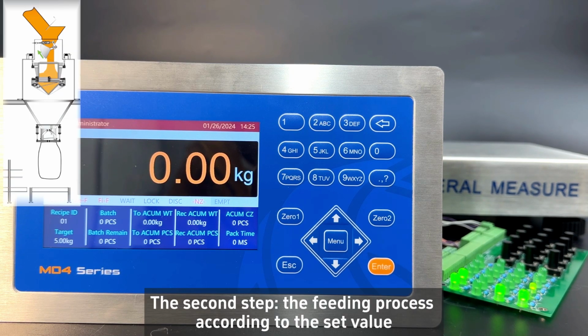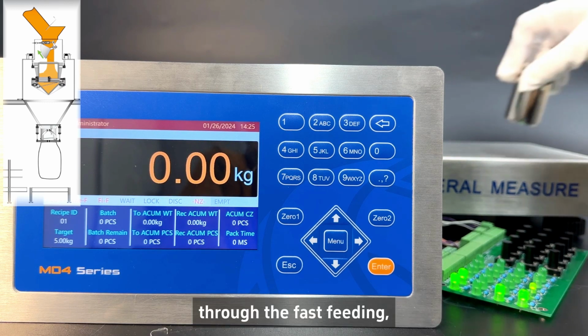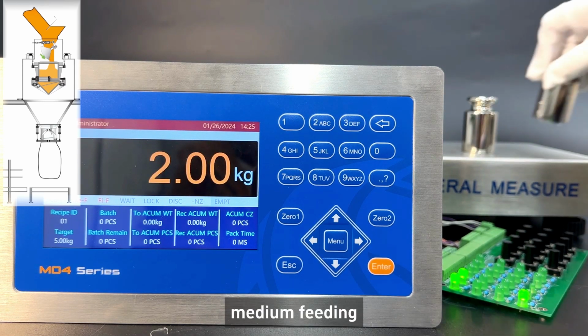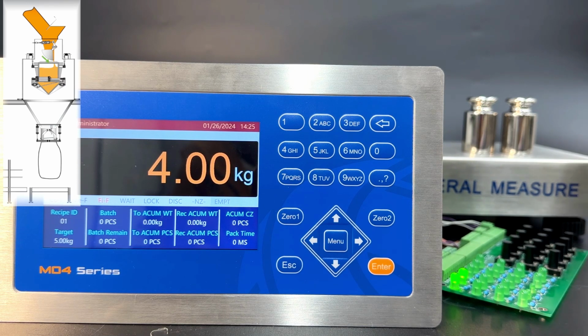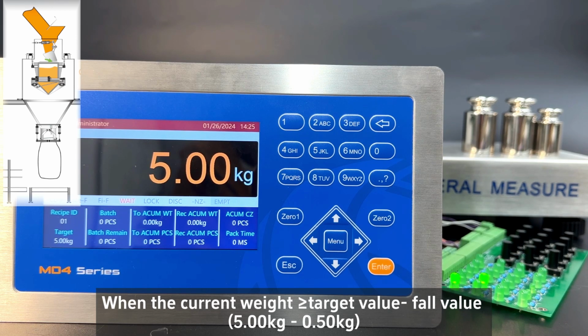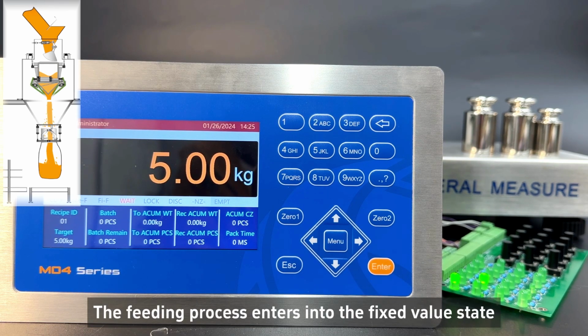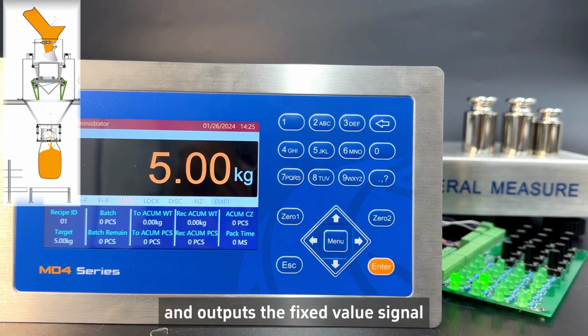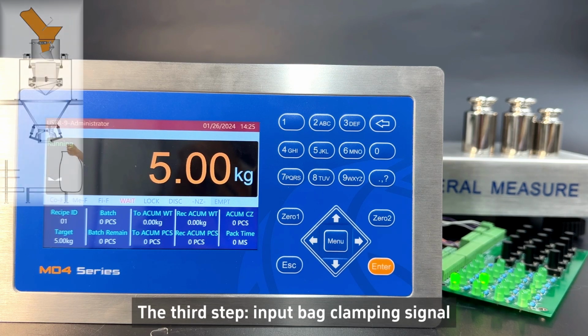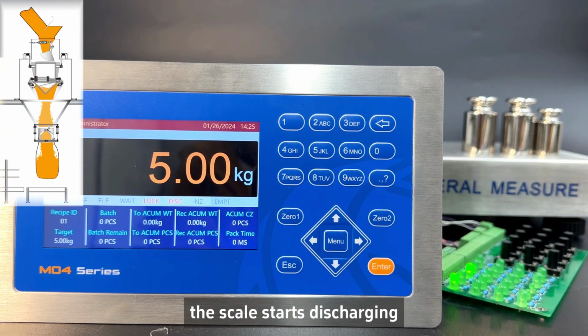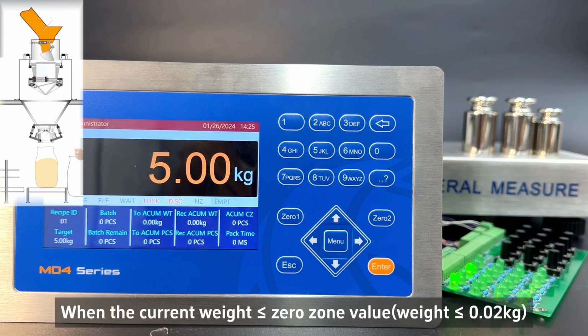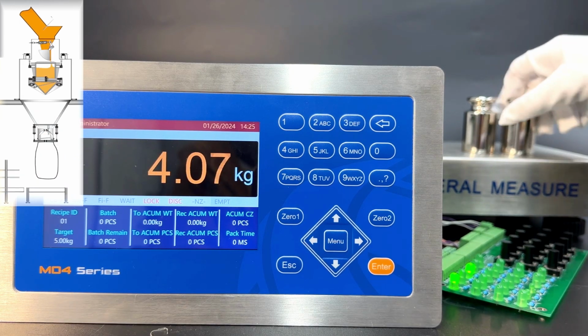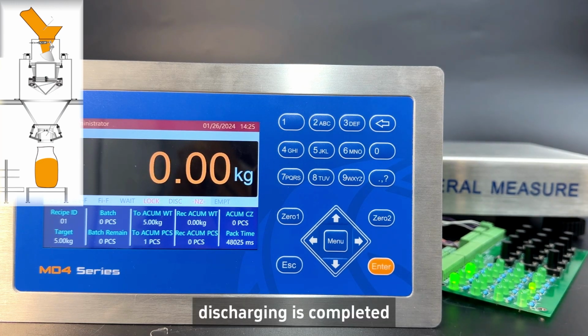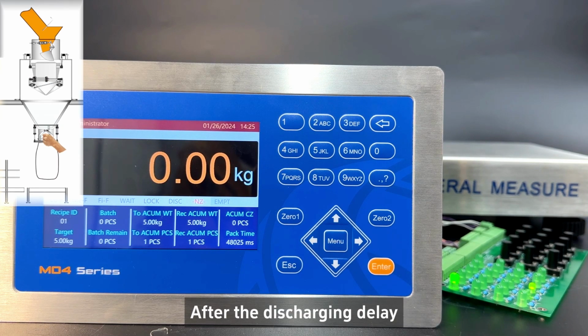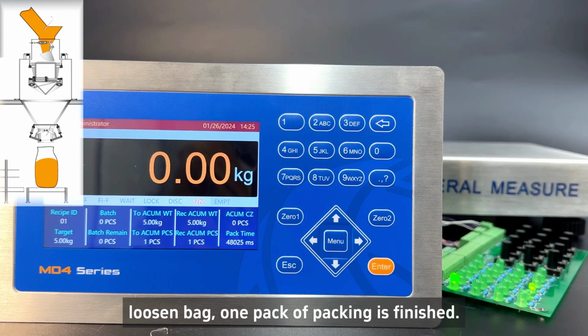The second step, the feeding process, according to the set value, through the fast feeding, medium feeding, slow feeding. When the current weight equal or over target value minus fall value, the feeding process enters into the fixed value state and outputs the fixed value signal. The third step, input bag clamping signal. The scale starts discharging when the current weight equal or under zero zone value. Discharging is completed. After the discharging delay, loosen bag. 1 pack of packing is finished.